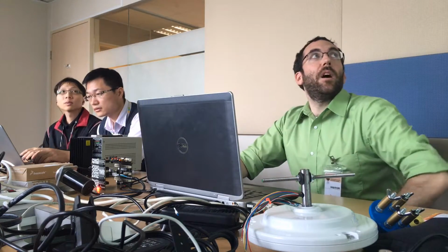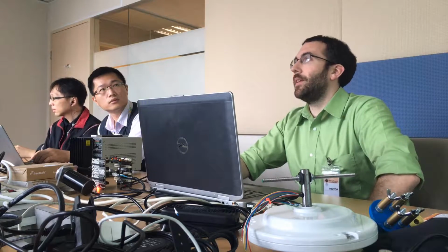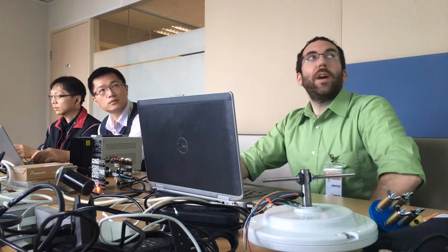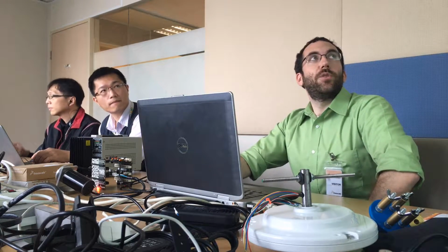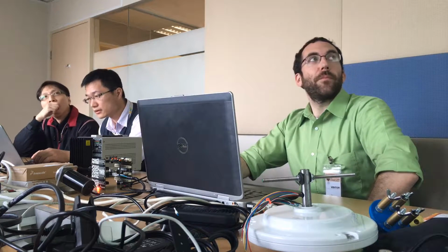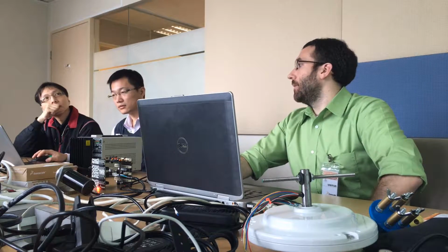The state is made up of the speed you want it to run, the minimum time to spend in the state, and then this if-then relationship table. Right now it's saying if no condition, so if true, go to low speed with this acceleration and jerk setting. But that's not what I want it to do. I want it to go to low speed if button is equal to 1. So I need to add a new if statement.